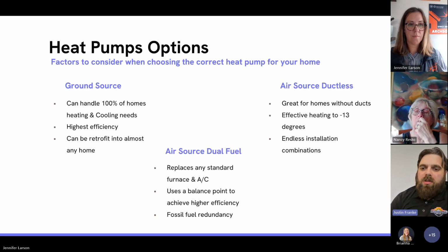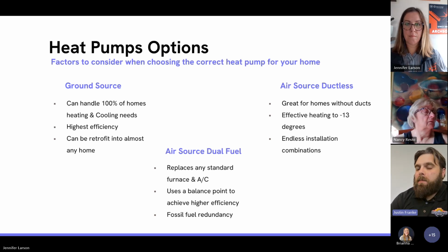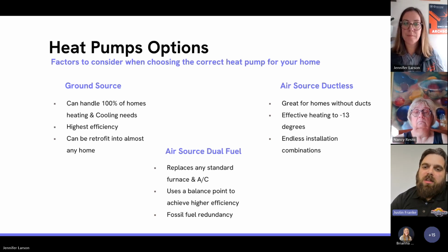It does use a balance point. When we combine it with solar, because we're not purchasing that portion of electricity to operate the machine, we can push the envelope a little lower before it transitions over to a fossil fuel as a heat source. The benefit is you have fossil fuel redundancy, so on super cold days, you're running on burning natural gas, LP, or any other heat source you have.